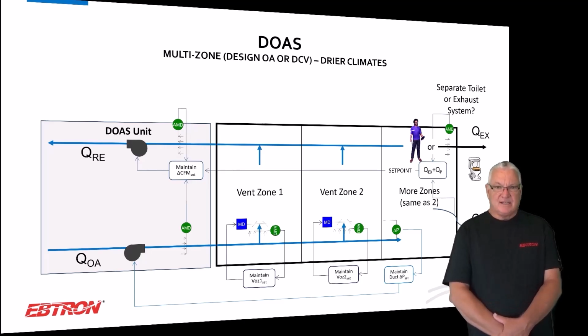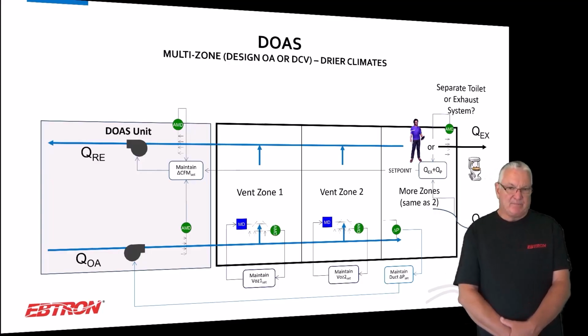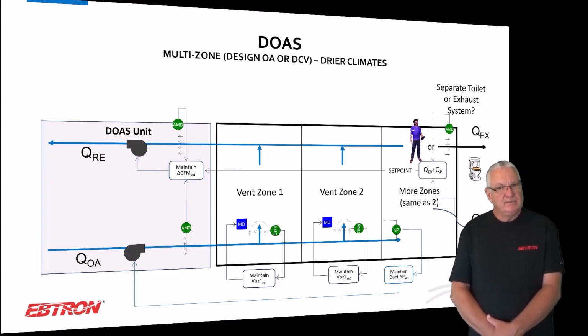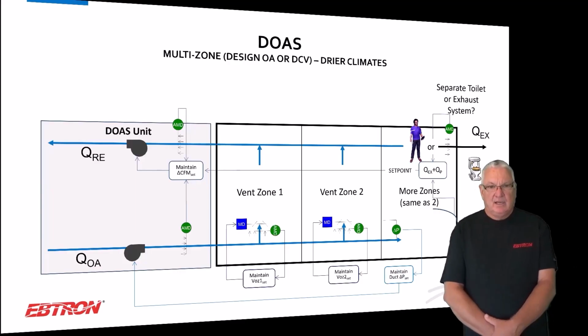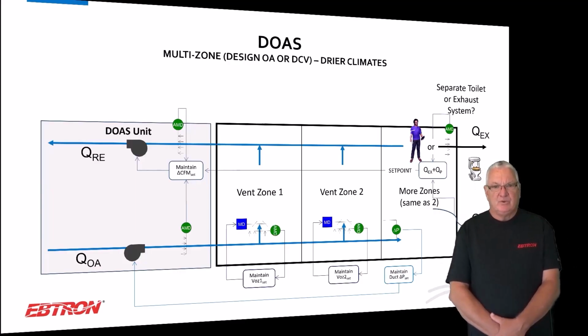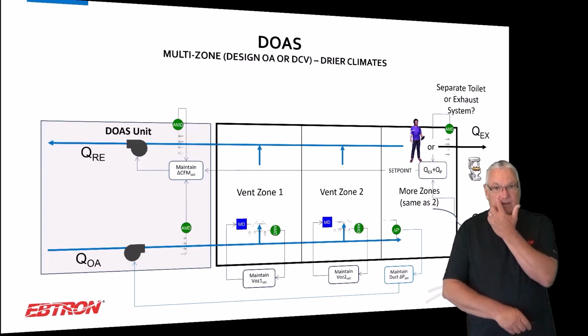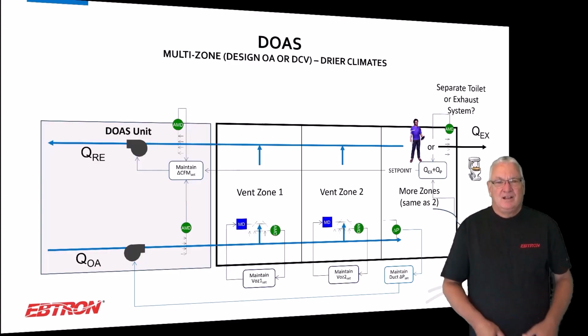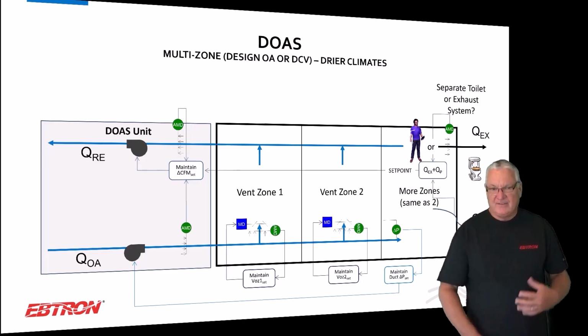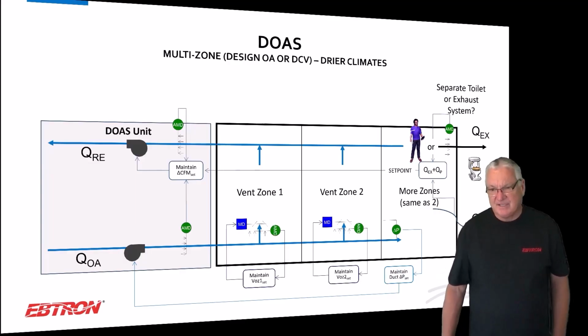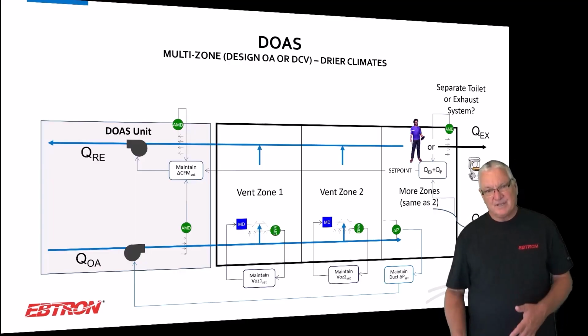When we get into DOAS designs, and this is more like schools, offices, theaters, things like that, but it's worth talking about because it still could be part of your design, particularly when you're doing DOAS. Okay, not DOAS, completely, when you're doing DCV, demand control ventilation. And demand control ventilation could be that you have a CO2 sensor in the space or you're doing some kind of occupancy counting, but it could be simple occupied, unoccupied type of DCV, like you just cut some ventilation zones off.